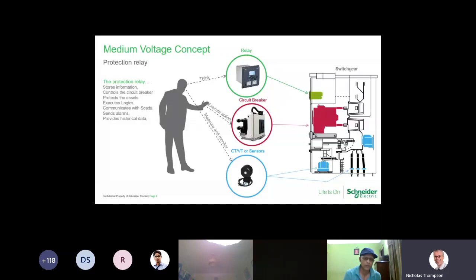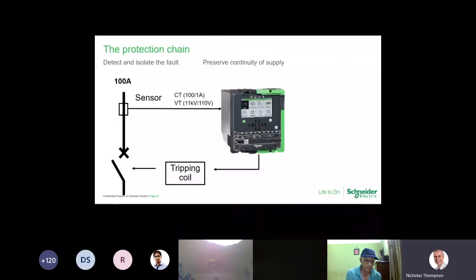So that's the concept. Now, protection relays come in different forms. For primary distribution switchgear, we're going to see a lot more functionality in the protection relay. It might have logic in there. It might be connected to communications and ultimately onto SCADA. If you're on SCADA, it's going to be sending alarms out if something's occurring, but doesn't necessarily need reactive action to trip the circuit breaker. And if you've got the right kind of relay, you will ultimately be able to retrieve what's been going on with it. I'll come on to more as to what we can do with protection relays as we go through. So here's the basic principle.